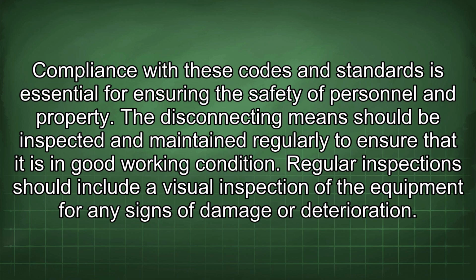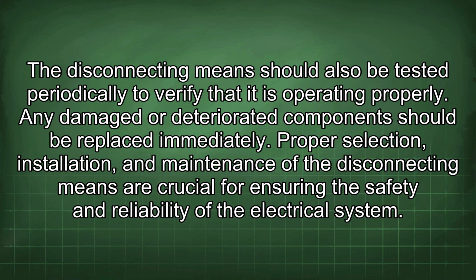The disconnecting means should be inspected and maintained regularly to ensure that it is in good working condition. Regular inspection should include a visual inspection of the equipment for any signs of damage or deterioration. The disconnecting means should also be tested periodically to verify that it is operating properly. Any damaged or deteriorated components should be replaced immediately. Proper selection, installation, and maintenance of the disconnecting means are crucial for ensuring the safety and reliability of the electrical system.